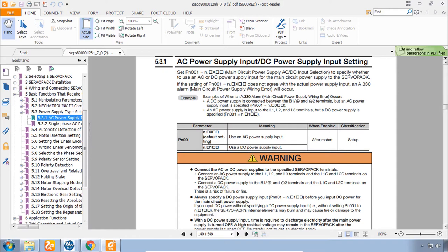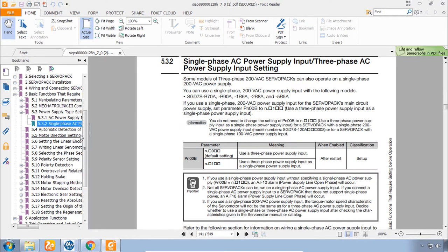But if you have a DC power supply then you can connect all of your axes together with the same supply and share the DC bus. And in some cases that will eliminate the need for regen resistors. Now single phase or three phase parameter. Also a simple setting.